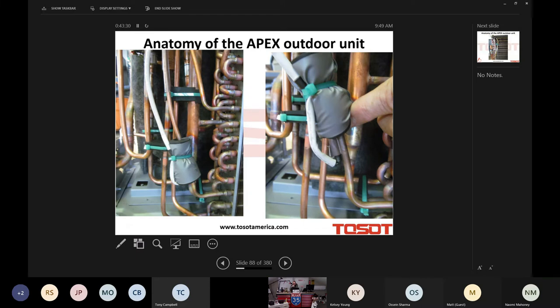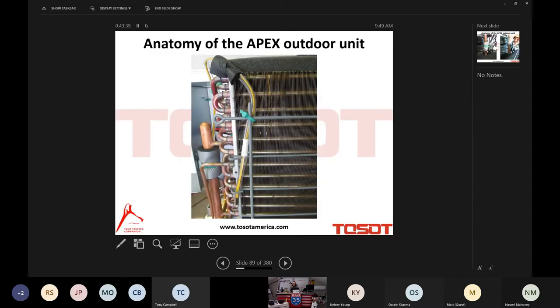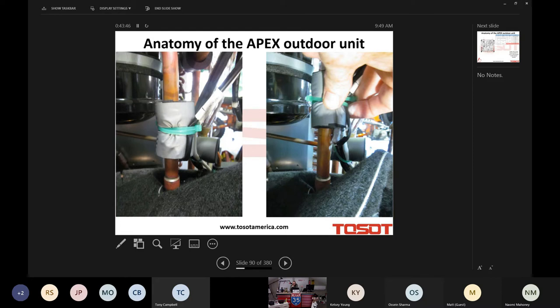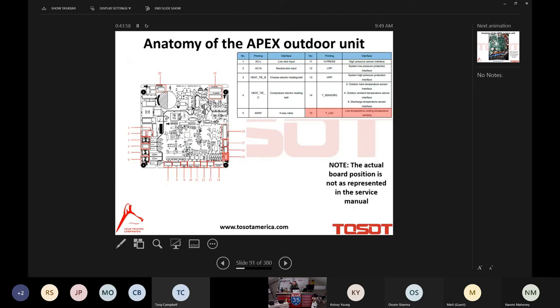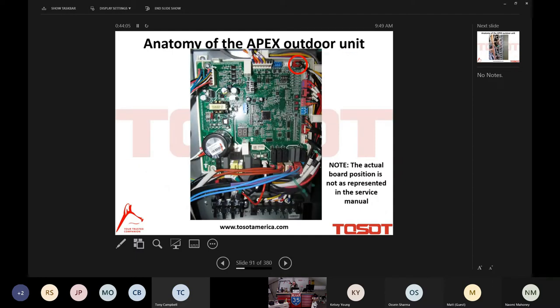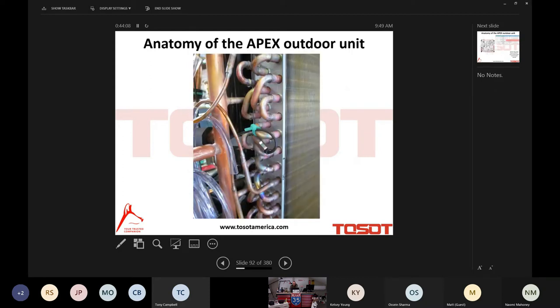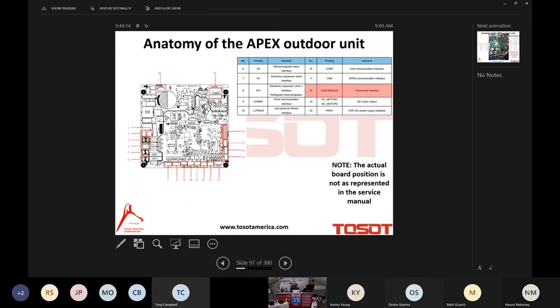Here is the heat exchanger temperature sensor, if you will, the coil temperature sensor at the bottom of the coil of the outdoor unit. Here is your outdoor ambient temperature sensor, just kind of hangs from the outdoor unit. And lastly, this is your discharge temperature sensor. Again, discharge being the discharge of the compressor. You can see that it is attached literally to the discharge tube coming off the top of the compressor. And the fourth and last of the thermistors of the outdoor unit is the low temperature sensing thermistor. It's separate from the other three, or at least its connection to the board is separate from the other three. And there you can see it there at one of the U-bends of the coil of the outdoor unit.